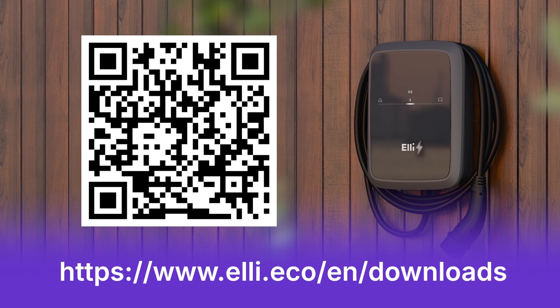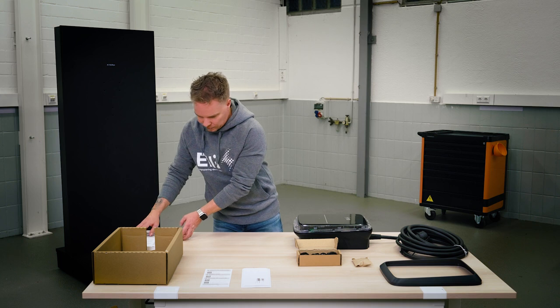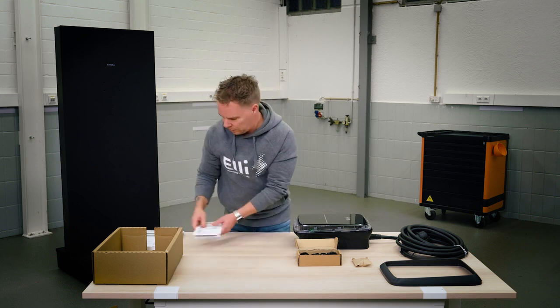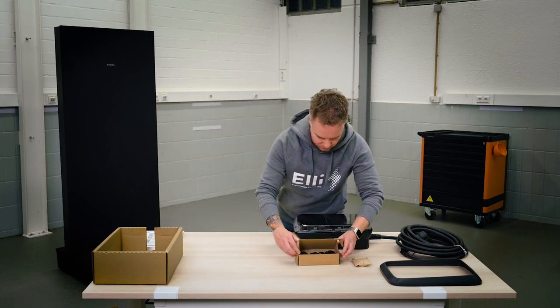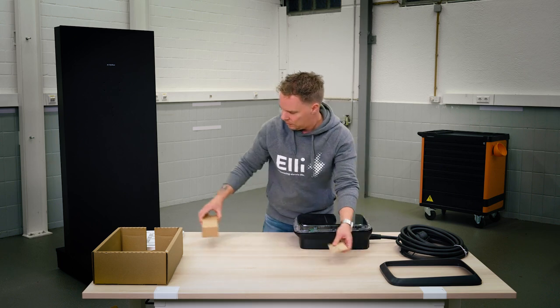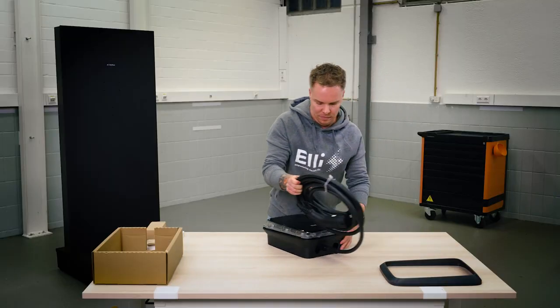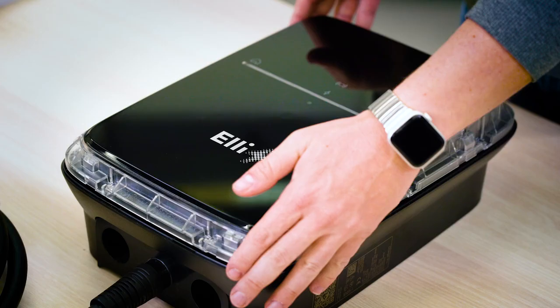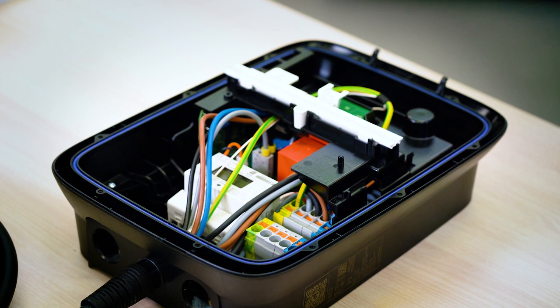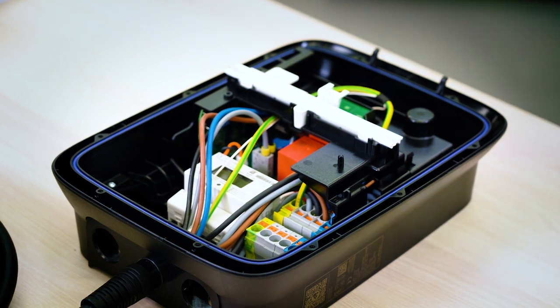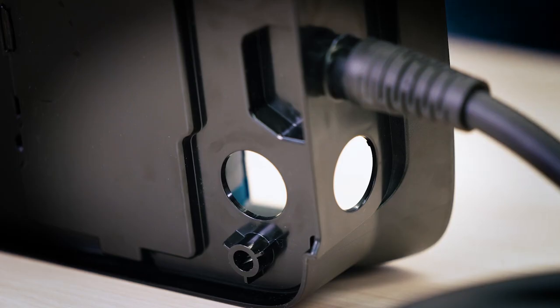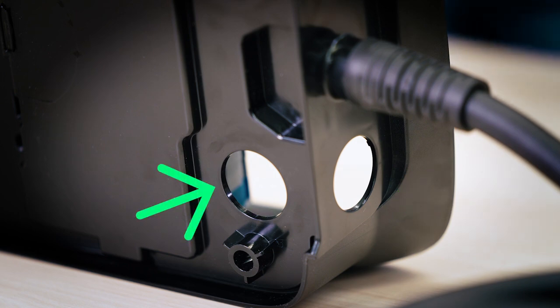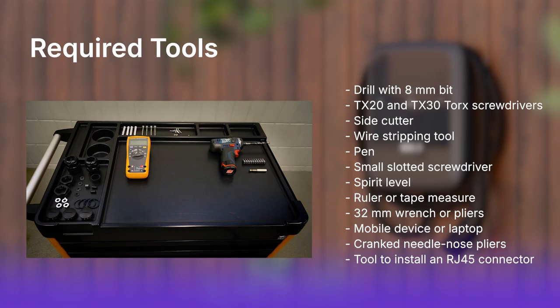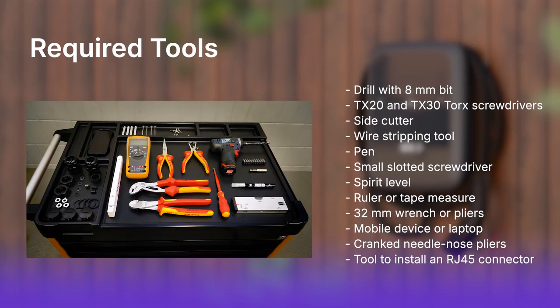Before you begin, please note that the wall box installation should only be performed by a certified professional. Select a suitable location to install the wall box. It should be protected from weather and direct sunlight. The wall must be able to support at least 40 kilograms. The Elli Charger 2 offers 2 options to install the power cable. It can be inserted from the bottom or from the back. To install the Elli Charger 2, you will need the tools displayed here.